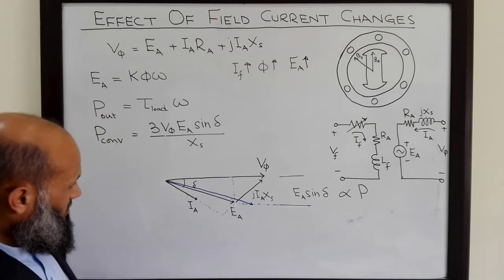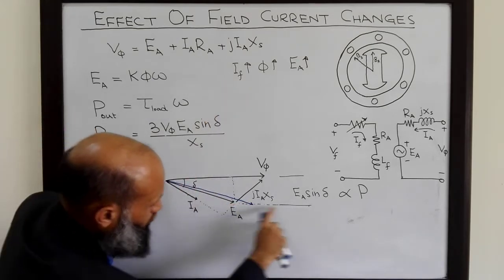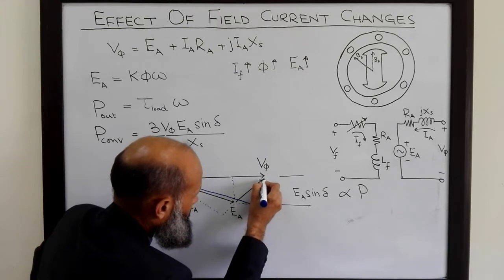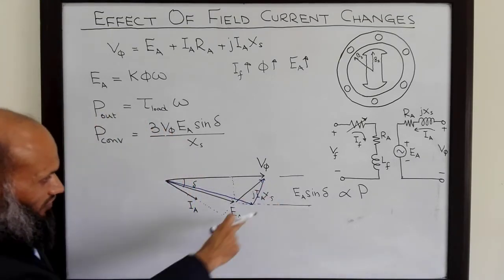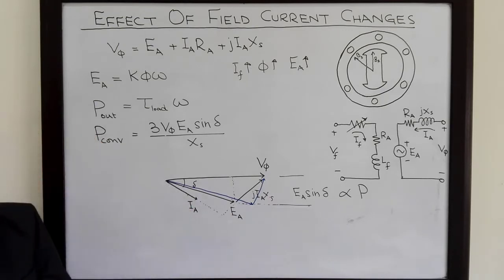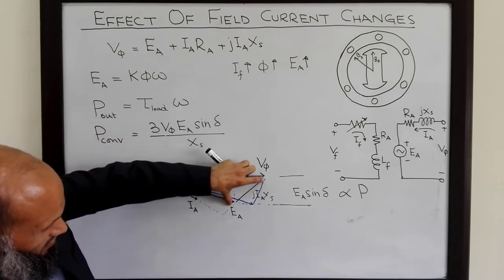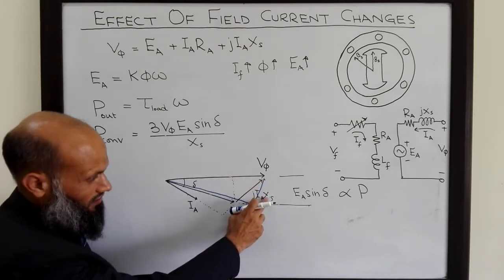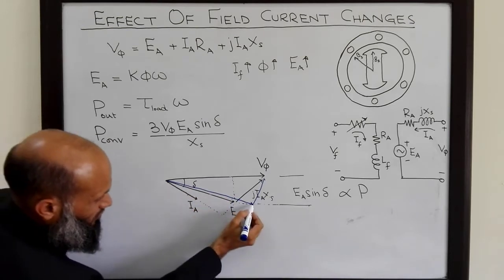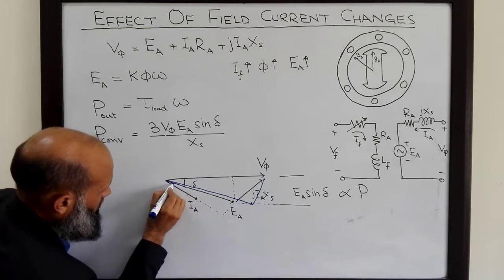When If is increased, Ea will increase in length. This new Ea phasor — call it Ea2 — moves along this horizontal line. Since Xs is constant and the jIaXs phasor is shorter, Ia will decrease. The new current Ia2 will be perpendicular to the new jIaXs phasor and will have smaller magnitude than Ia1.